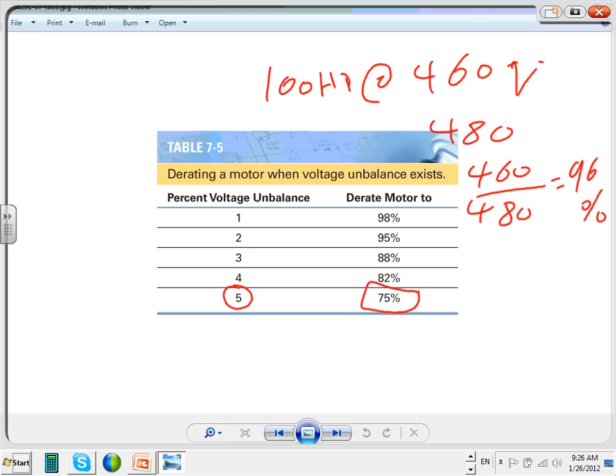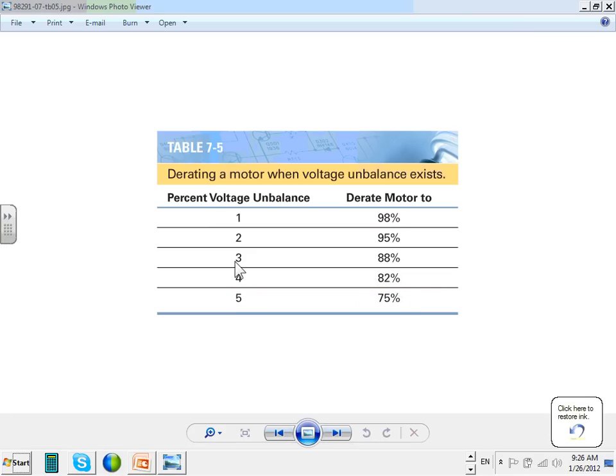Did they come up with something similar? 96? Yeah, 96%. So they allow you to dip down, and still the motor doesn't even feel it. You can still dip even lower because the motor is rated for 430. That's how they handle the voltage differences. They rate them at a lower voltage than the nominal voltage.